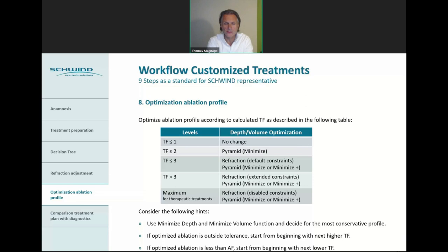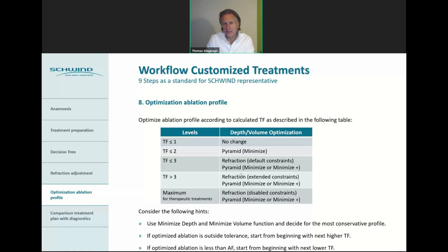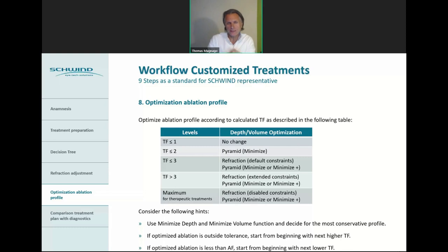If the optimized ablation is outside the tolerance, start from the beginning with the next higher tolerance factor. If the optimized ablation is less than aberration-free, start with the next lower tolerance factor. So we may run through this procedure — the first seven or eight steps — multiple times, though normally it's only once. This is what we always check for.